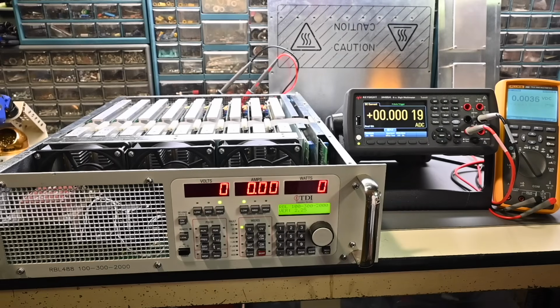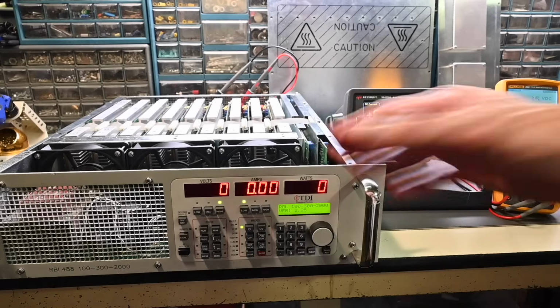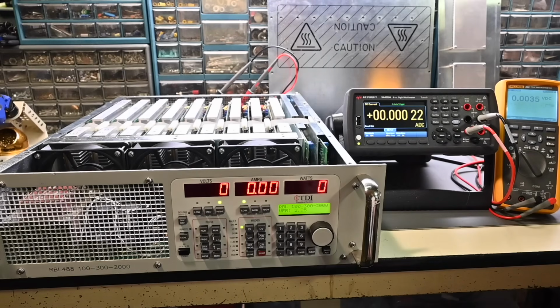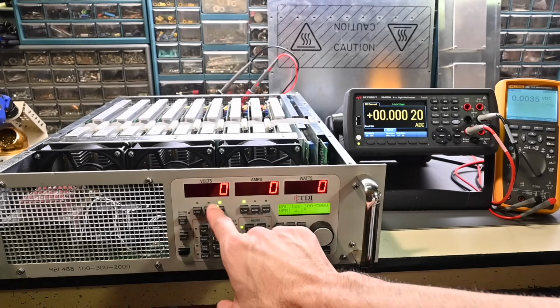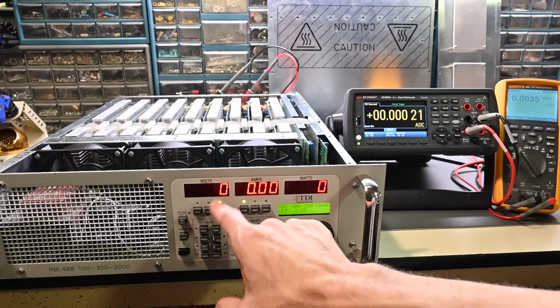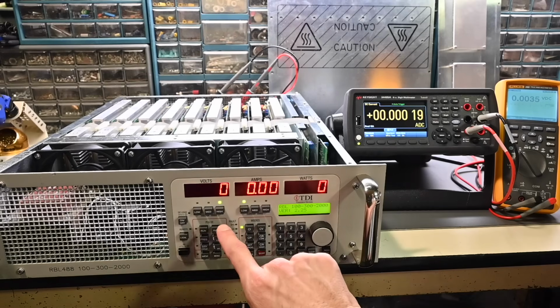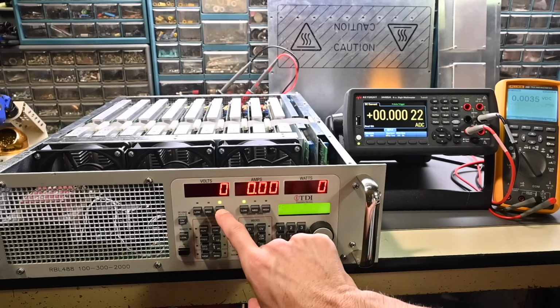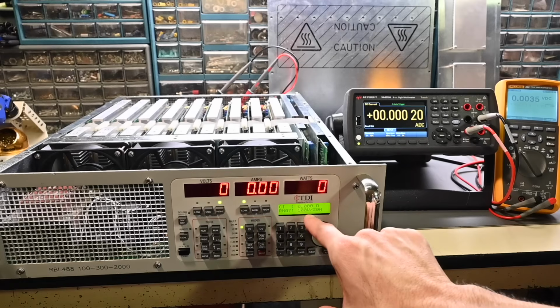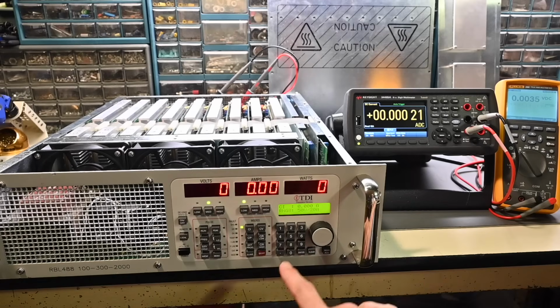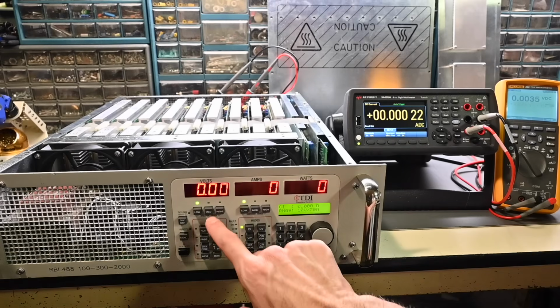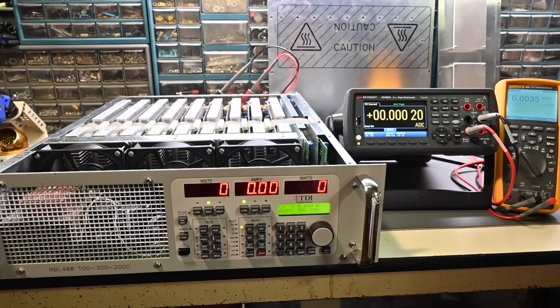Let that start up. Probably hear that other fan kicking in, so fans are running here, fans over in the power supply. Now before I turn on the voltage from the power supply, this range right here where it says low, medium, and high is of course the voltage range that you're using. So right now it's in the high range, and you can see it says 100 volts and then 20 amps. If I go to medium range, then that's 50 volts maximum, and then the low range is 10 volts. So I'll put this in the medium range because we won't be going over 50 volts. So it changes the resolution that you have on the display.